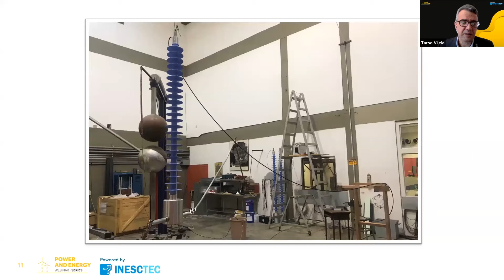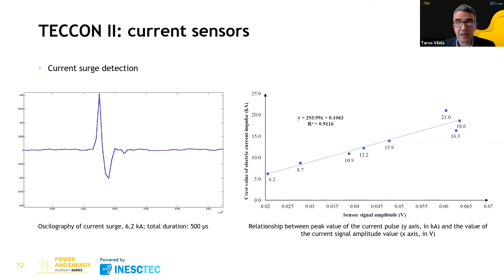Could you please go to the next slide? And here is the result. As you can see, the sensor was able to detect the impulse here in the graphic on the left, and on the right, we checked the relationship between the peak value of the current pulse and the value of the current signal amplitude. So we can see we have a good correlation, and the sensor is able to detect even very fast phenomena. Next slide, please.